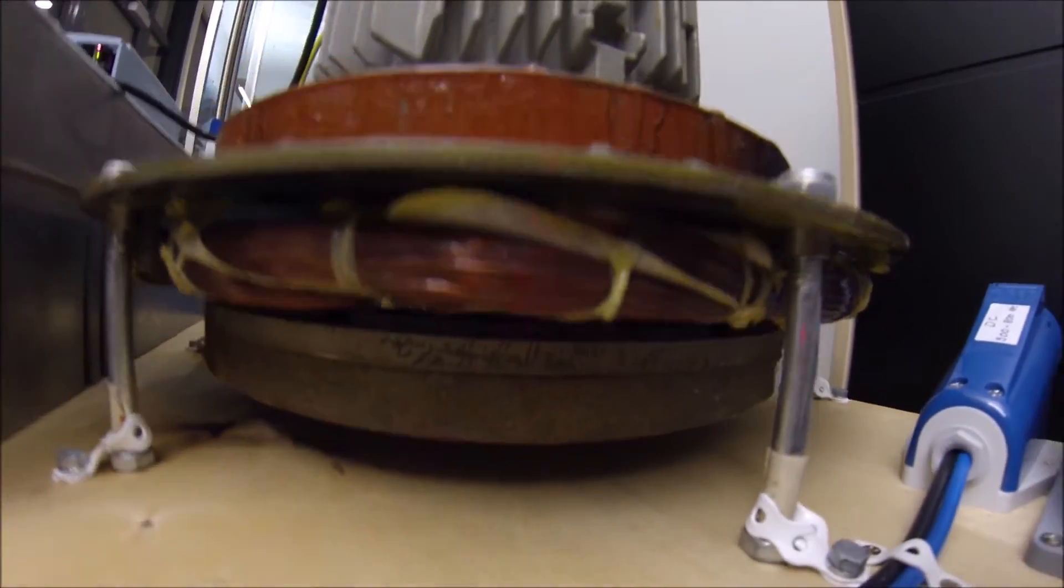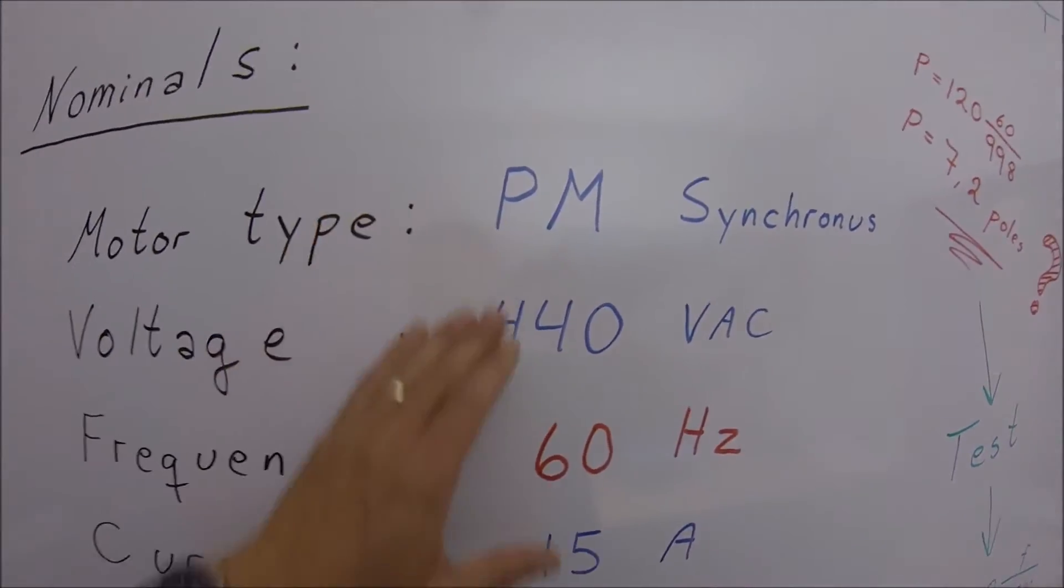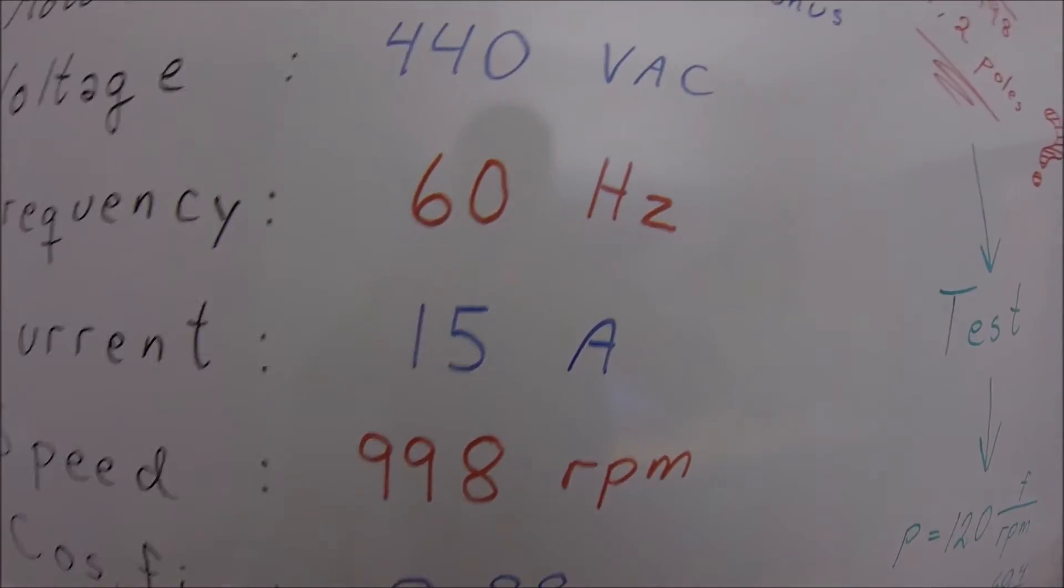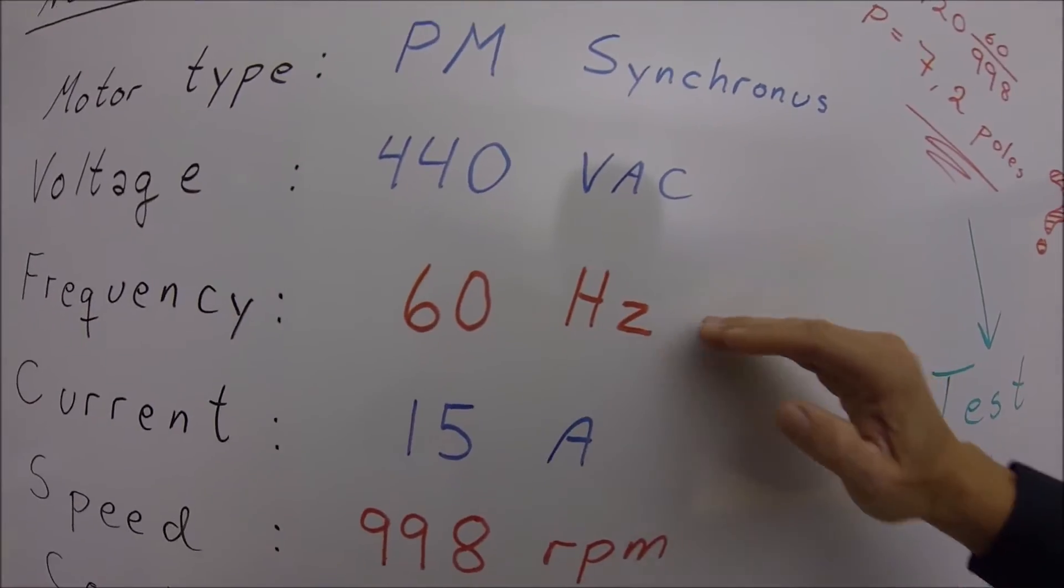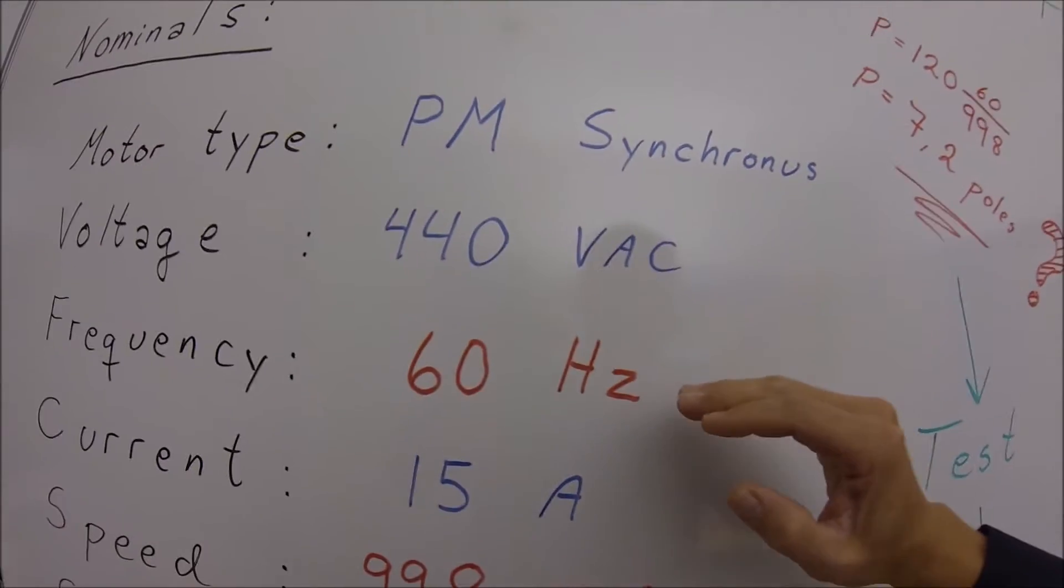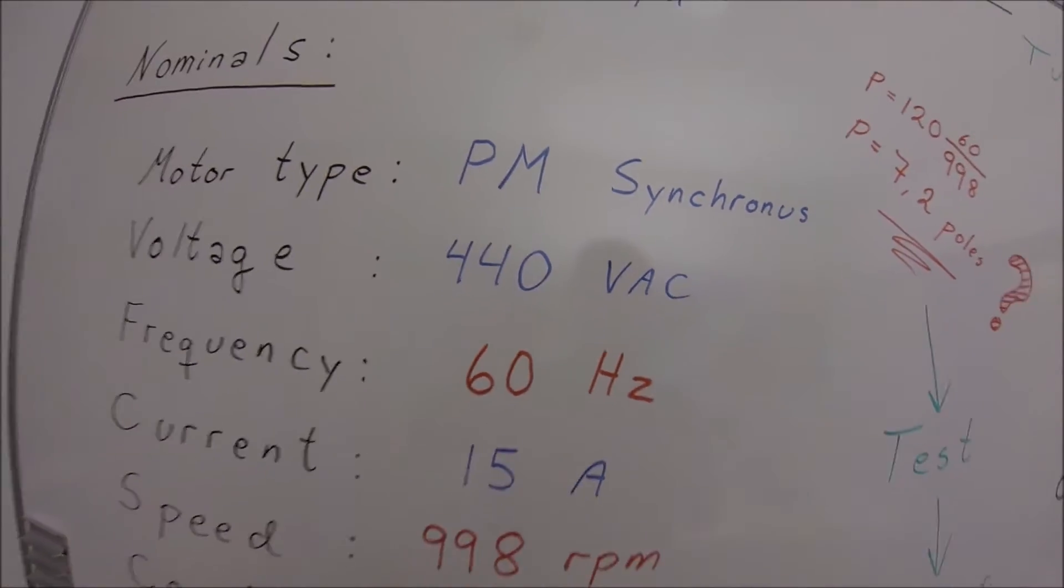To achieve a correct tuning we need to know the motor nominal data. The motor vendor have given me this data. Are they right? Are they precise enough? Especially the relation between the frequency and RPM is important, and also the relation between the frequency and the voltage, which is the BEMF curve. Let's check.